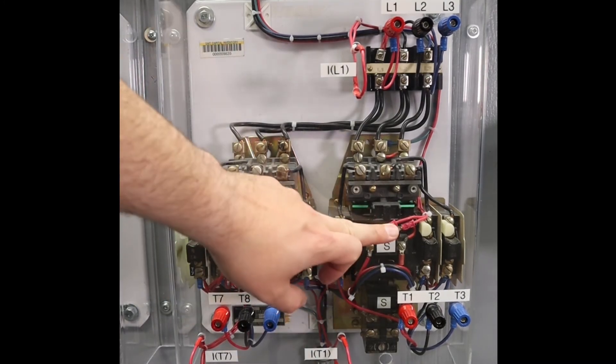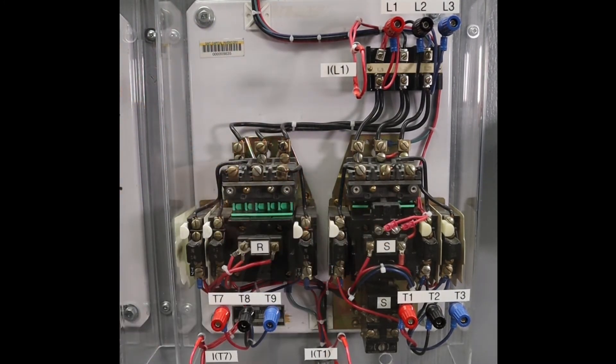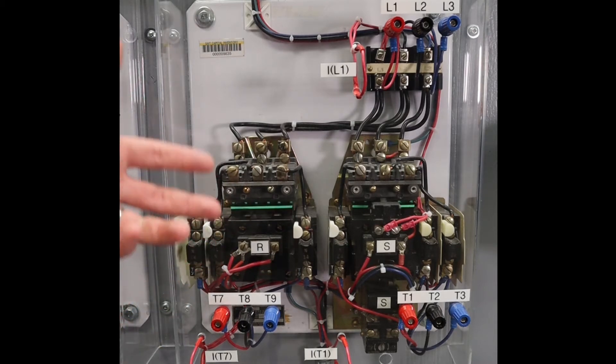is my S coil energizes, which would be running one half of the motor. After a period of time, then my R coil is going to close. Now it's energizing both halves.